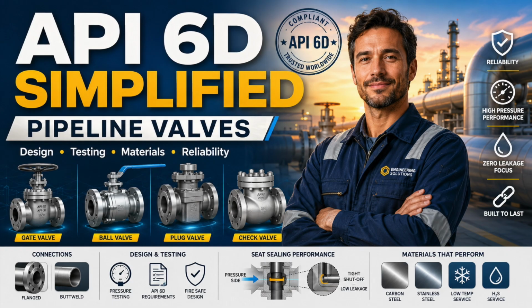Gate valves can provide excellent full opening passage, but the generic label tells you very little. Is it wedge, slab, expanding, or double disc? Does it seal in one direction or both? How are the seats energized? Can cavity pressure build? Can the cavity relieve? Does that relief compromise isolation? Can the stem sealing system be maintained? Can solids collect in the body? Will the valve operate after years without movement? Does it need sealant injection? A gate valve that performs perfectly in a factory may behave very differently after years in buried service.